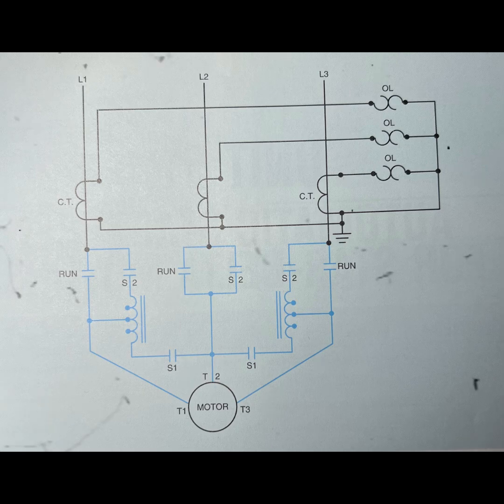The motor is disconnected momentarily from the line during the transfer from the start to the run condition. Closed transition connections are usually found on standard size 6 and larger starters. For those who are not familiar with starters, starters come in sizes like size 0, 1, 2, 3, 4, 5, and in this case 6. So we said the closed transition connections are usually found on the standard size 6 and larger starters.